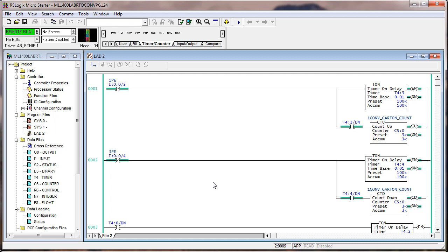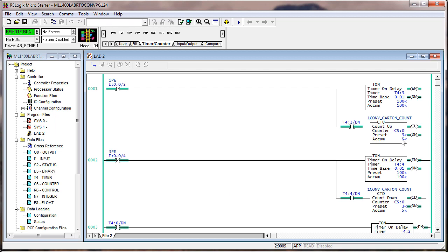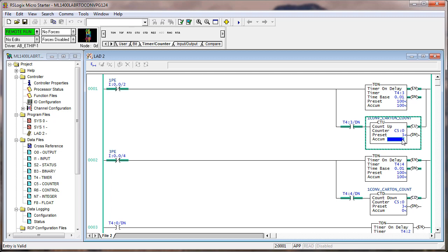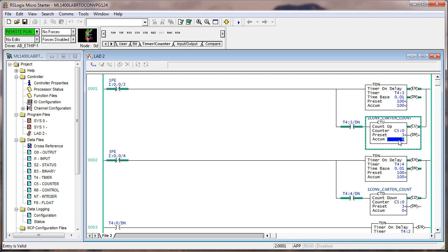The other thing that the timer does, if I were to flicker 1 PE, which is input 2, so watch closely. If I flicker it, see it doesn't count up until it hits the final. Okay, we're way over count now. I don't know if you caught all that. But if I tap input 2 really fast, it's only going to take the last one and count it. See, I've only got a count of one there. What that does is that eliminates counting bobbles. When things move on the conveyor, they don't move necessarily really smooth. The conveyor may itself have some bumpy surface underneath the belt.